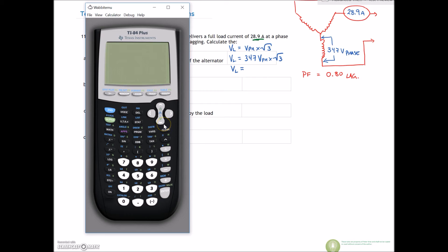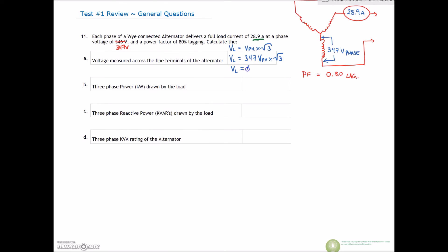You can see how little things will screw you up — I was dividing instead of multiplying. You know that the voltage on the line has got to be greater than the voltage on the phase. So instead of dividing, we're supposed to be multiplying 347 by √3, which gives us 601 volts. We'll take that as 600 volts — that's our standard voltage. So we have a line voltage of 600 volts from line to line.